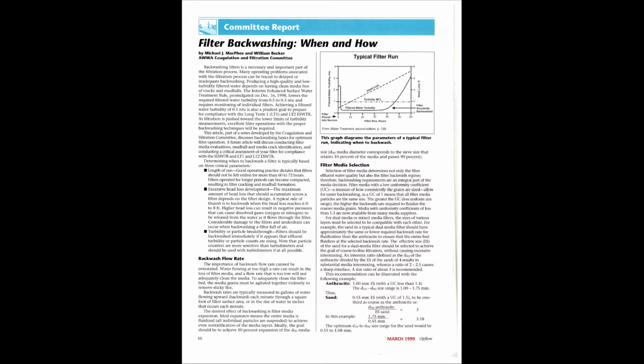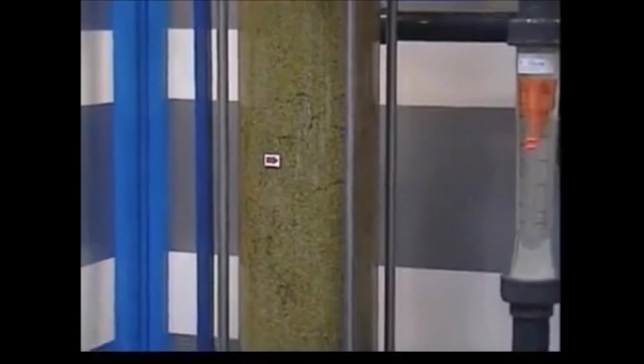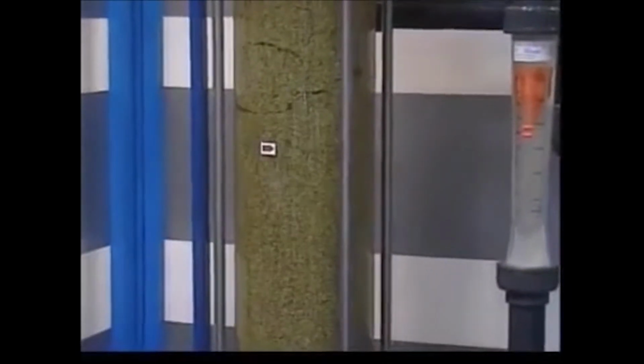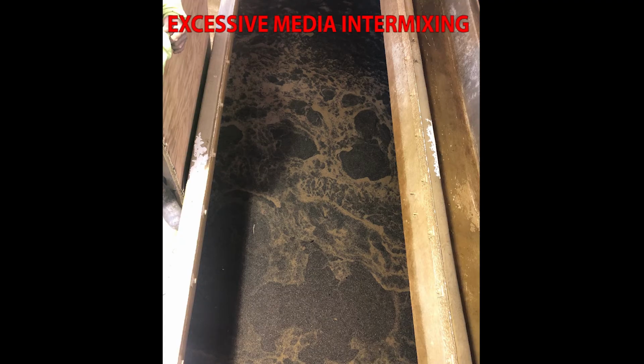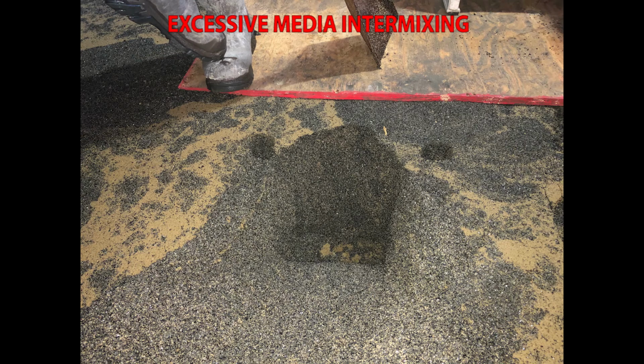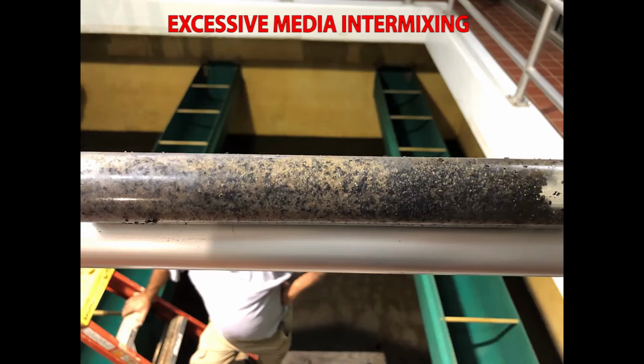An AWWA OpFlow article from March 1999 provides important guidance regarding relative sizes of sand and anthracite. To ensure that the entire bed fluidizes at the selected backwash rate, the sand must have approximately the same or lower required fluidization backwash rate as for the anthracite. The effective size of the sand should be selected to provide coarse-to-fine filtration without causing excessive intermixing.